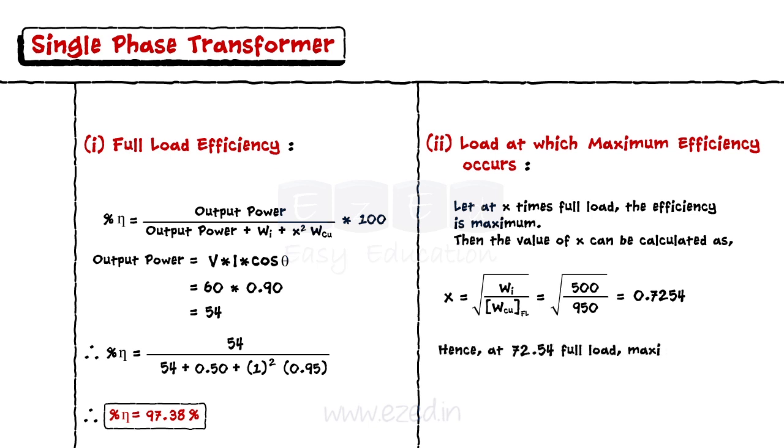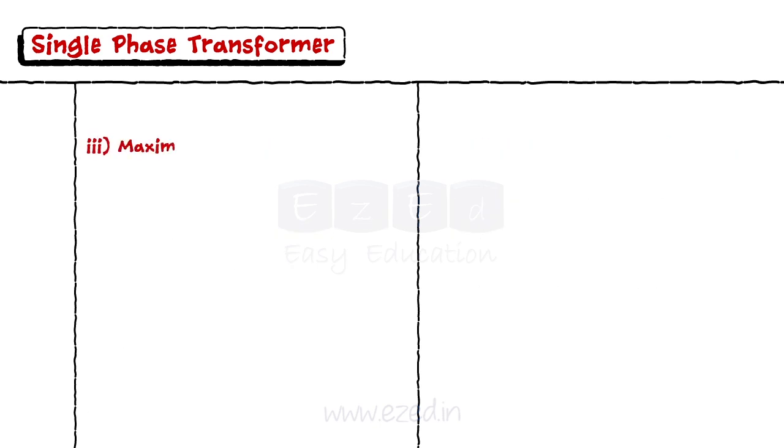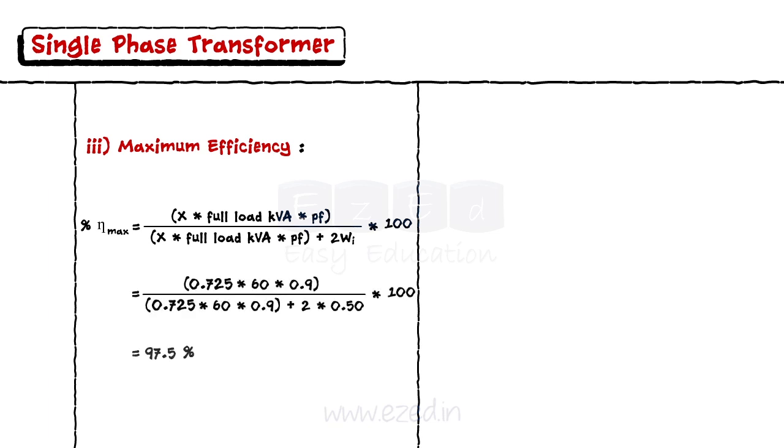Thus, at this load, we achieve maximum efficiency. The formula for maximum efficiency is: x times full load kVA times power factor upon x times full load kVA times power factor plus 2 times core loss, times 100. Putting all the values, we get the maximum efficiency equal to 97.5%.